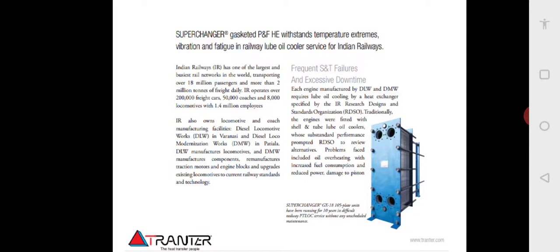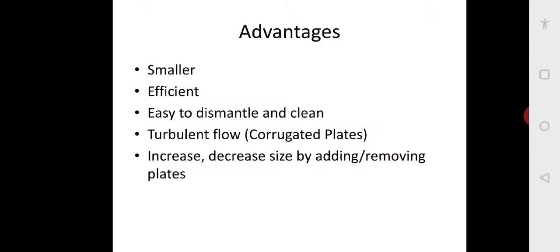These heat exchangers are very efficient, occupy less space, and because they are gasketed with polymer gaskets, they can withstand vibrations in addition to high temperatures. The advantages of plate type heat exchangers are: they are small, compact and efficient; very easy to dismantle; the corrugated plates provide turbulent flow, improving the convective heat transfer coefficient H; and you can increase or decrease the size just by adding or removing plates.